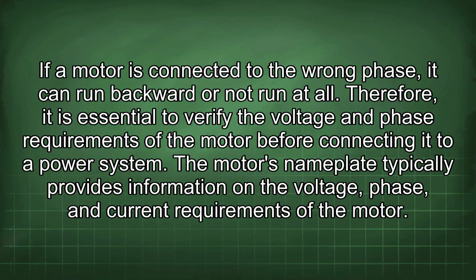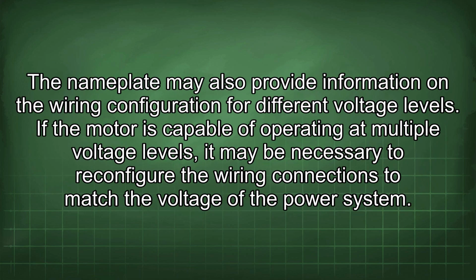If a motor is connected to the wrong phase, it can run backward or not run at all. Therefore, it is essential to verify the voltage and phase requirements of the motor before connecting it to a power system. The motor's nameplate typically provides information on the voltage, phase, and current requirements of the motor. The nameplate may also provide information on the wiring configuration for different voltage levels. If the motor is capable of operating at multiple voltage levels, it may be necessary to reconfigure the wiring connections to match the voltage of the power system.